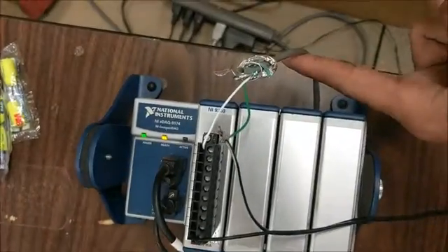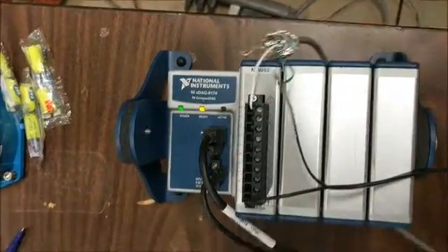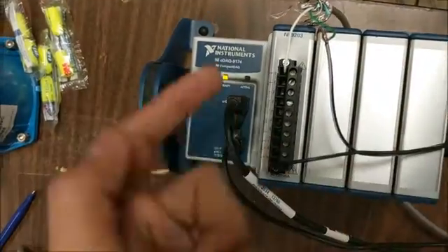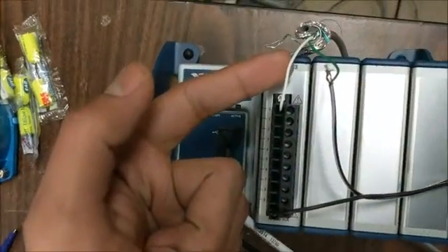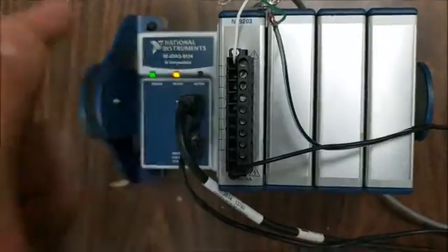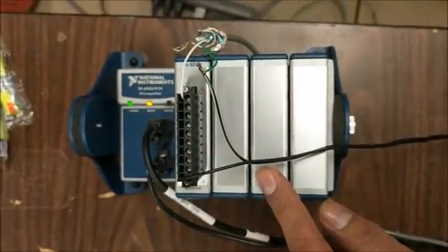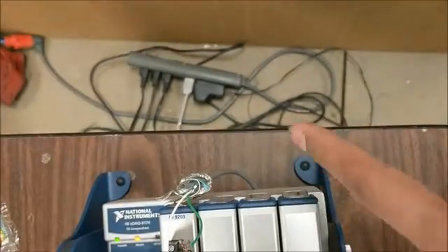The gray wire comes out of the pressure transducer, which has two separate wires. The green wire is positive and the white is common, which actually sends in current pulses, which are read by the data logger. The data logger itself needs a 12 volt DC supply, which is coming out of there.